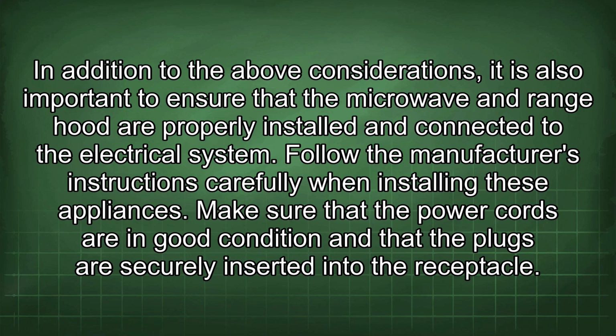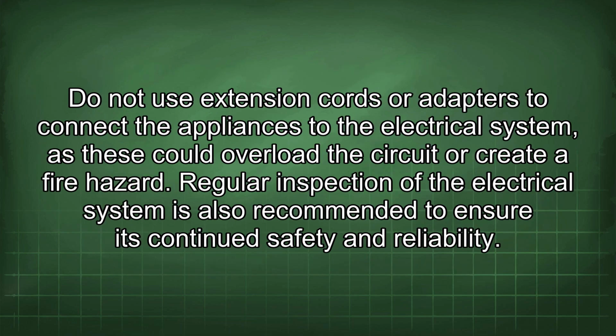The label should clearly indicate that the circuit is dedicated to the microwave and range hood only. In addition to the above considerations, it is also important to ensure that the microwave and range hood are properly installed and connected to the electrical system. Follow the manufacturer's instructions carefully when installing these appliances. Make sure that the power cords are in good condition and that the plugs are securely inserted into the receptacle. Do not use extension cords or adapters to connect the appliances to the electrical system, as these could overload the circuit or create a fire hazard.